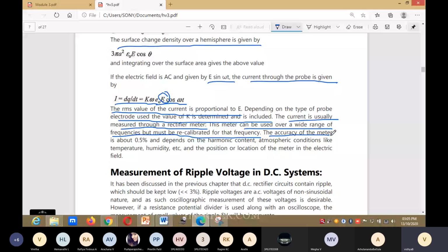The accuracy of the meter is about 0.5% and depends on the harmonic content, atmospheric conditions like temperature, humidity, etc., and the position or location of the meter in the electric field.